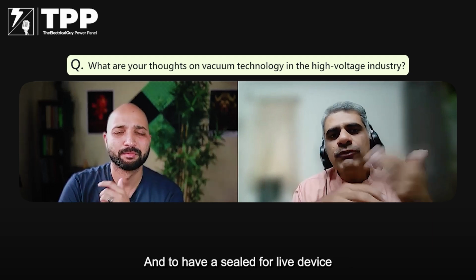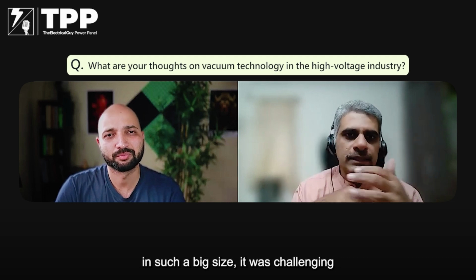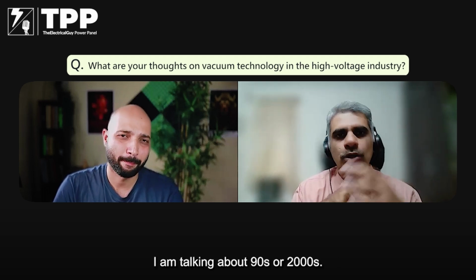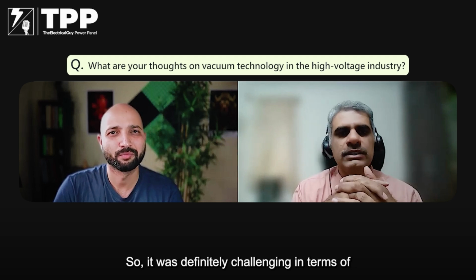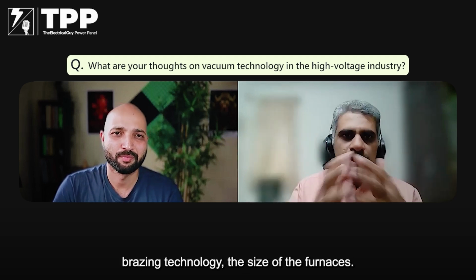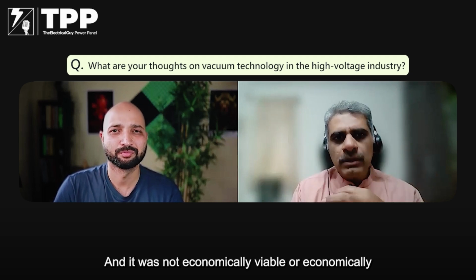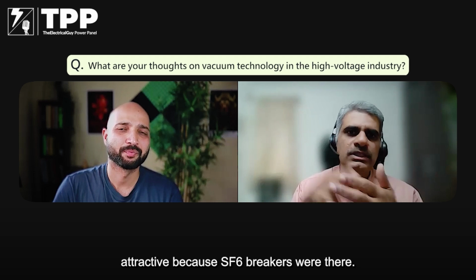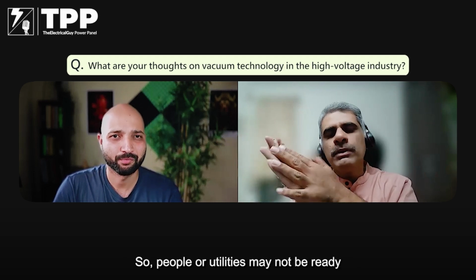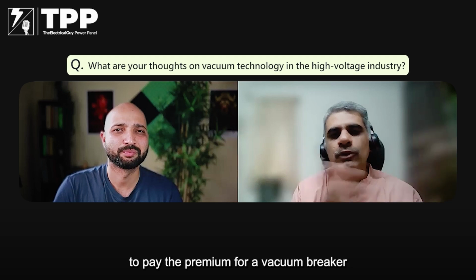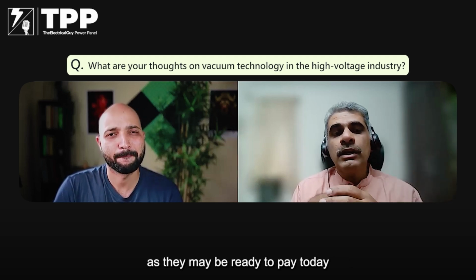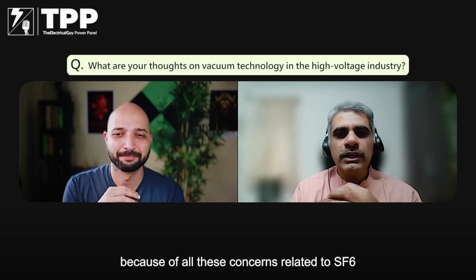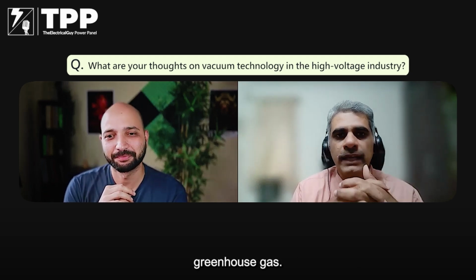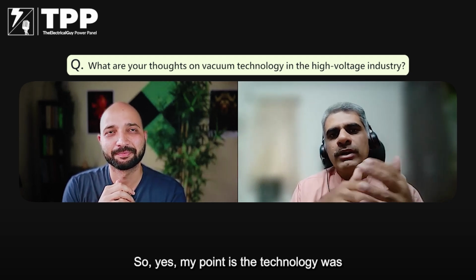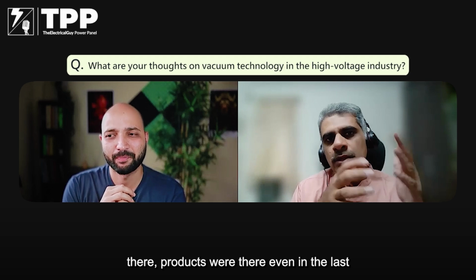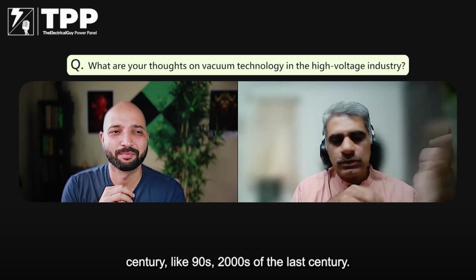And to have a sealed-for-life device in such a big size was a challenge in those times. I'm talking about the 90s or 2000s. So it was definitely challenging in terms of brazing technology and the size of the furnaces, and it was not economically viable or attractive because SF6 breakers were there. So utilities may not have been ready to pay the premium for a vacuum breaker as they may be ready to pay today because of all these concerns related to SF6 being a greenhouse gas. So yes, my point is the technology was there, products were there even in the last century, like in the 90s, 2000s of the last century.